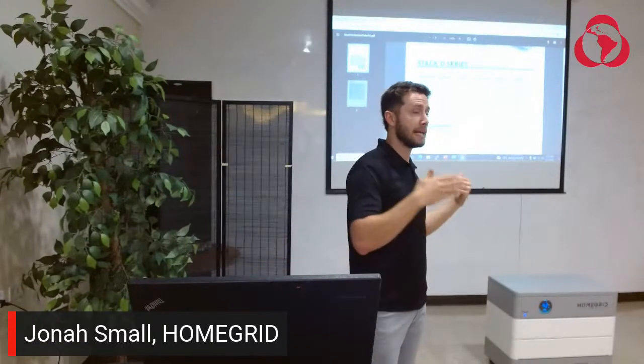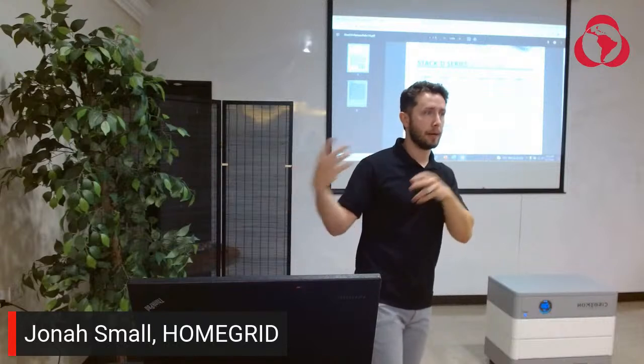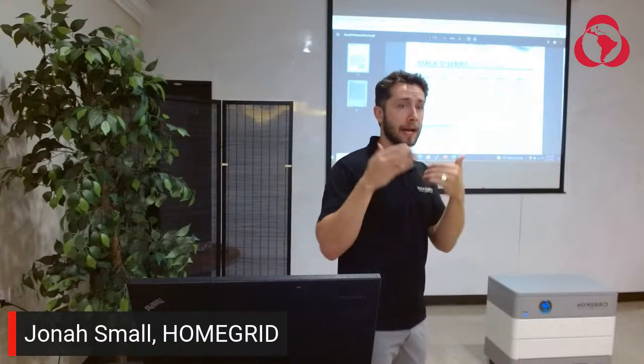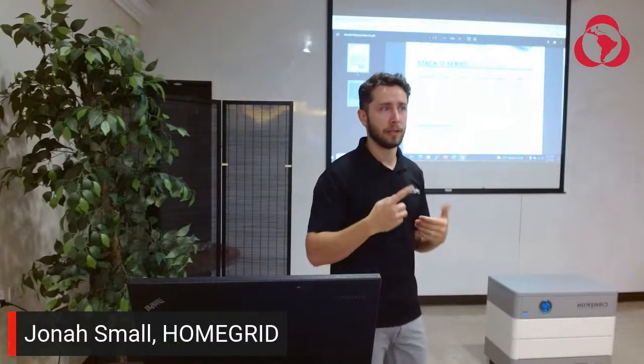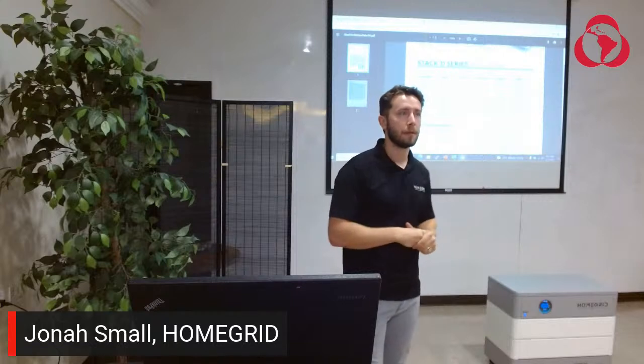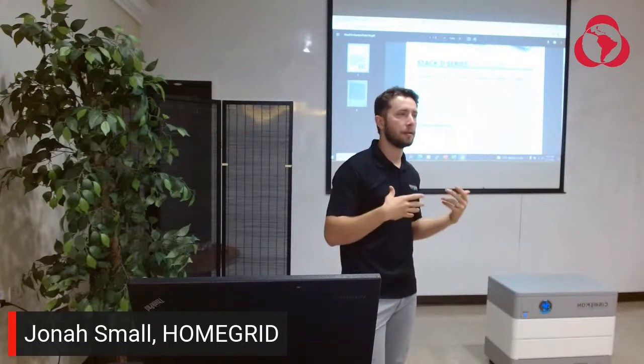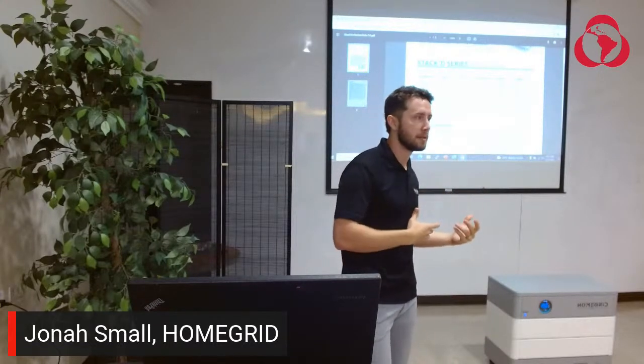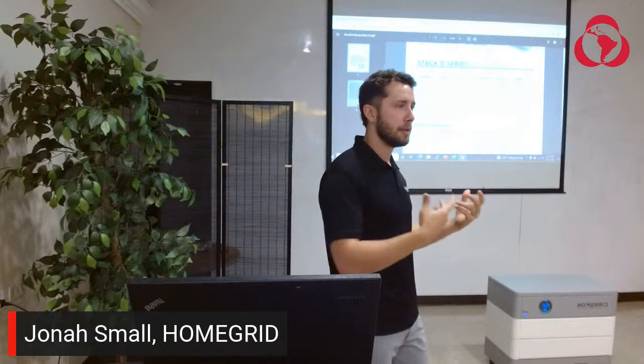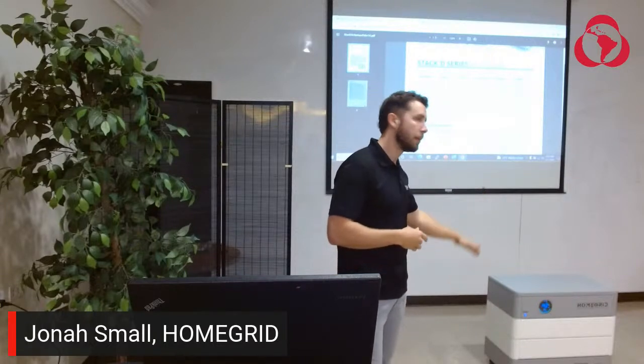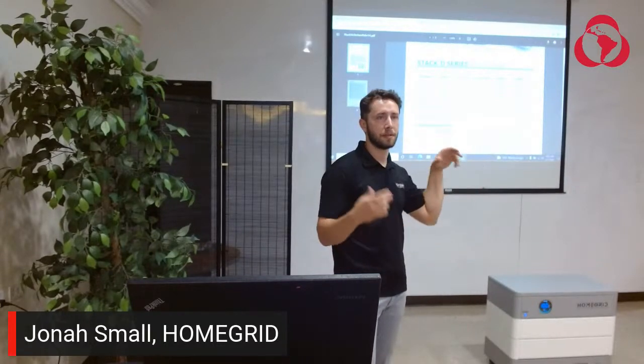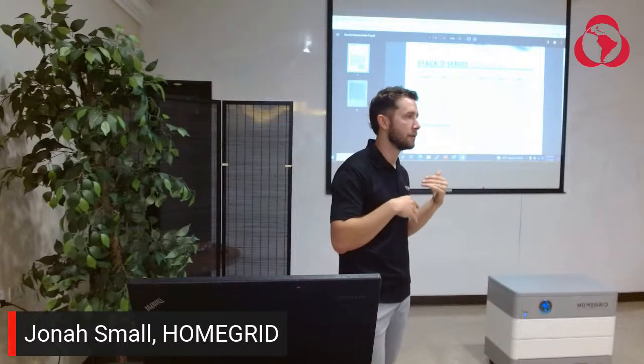So if you wait 9 years and add a module, that new module is only warranted for 1 year, since it's based on the initial install. But in terms of safety or battery health, you can add a module at any point, because these are wired in parallel and the BMS has safety protocols to handle voltage differences.